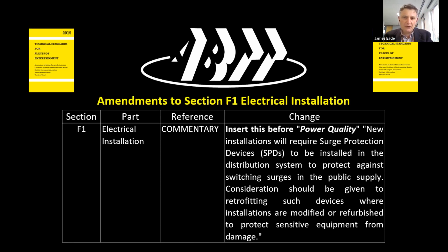A couple of other points on this. Do you need to replace dimmer racks? No, you don't. In the wiring regulations introduction, it says installations conforming to previous editions of BS 7671 are not necessarily unsafe, as long as they're properly maintained. There's no need to retrofit protective devices to bring them up to current standards. That's a big misnomer. As long as your installation is maintained and looked after, it doesn't necessarily become unsafe.